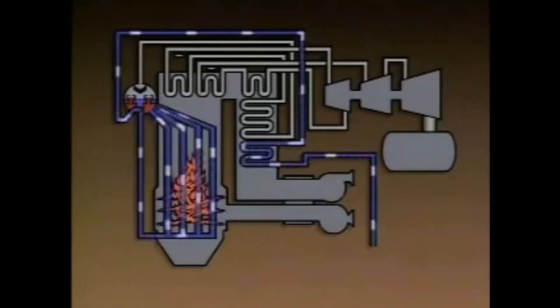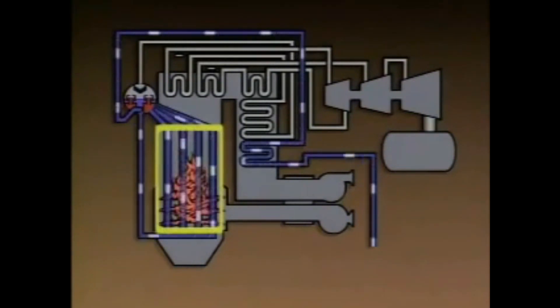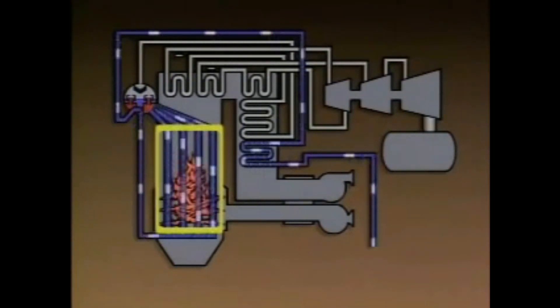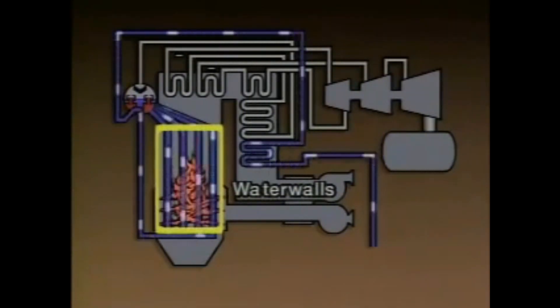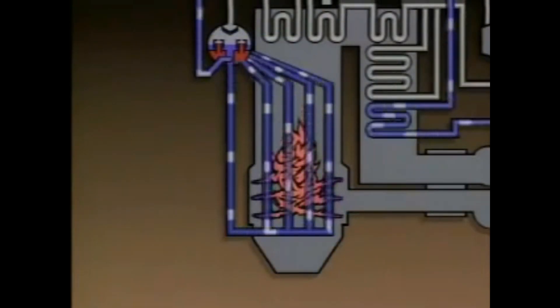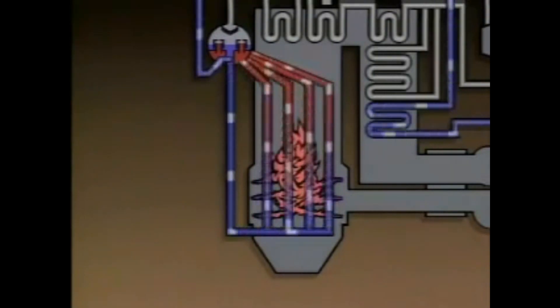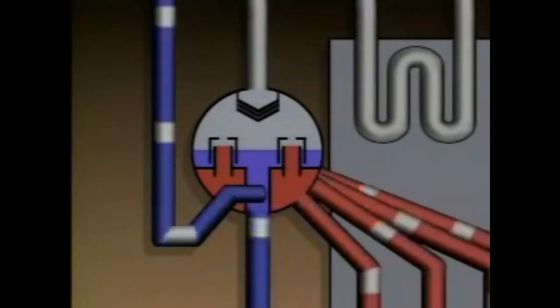The lower headers supply water to the bottoms of the boiler tubes. The boiler tubes, which line the inside walls of the boiler furnace, are commonly called water walls. The water walls are exposed to the heat produced by burning fuel. As water flows up through the water walls, heat turns some of the water into steam. The mixture of water and steam rises until it enters the boiler drum, where it is separated into water and steam.